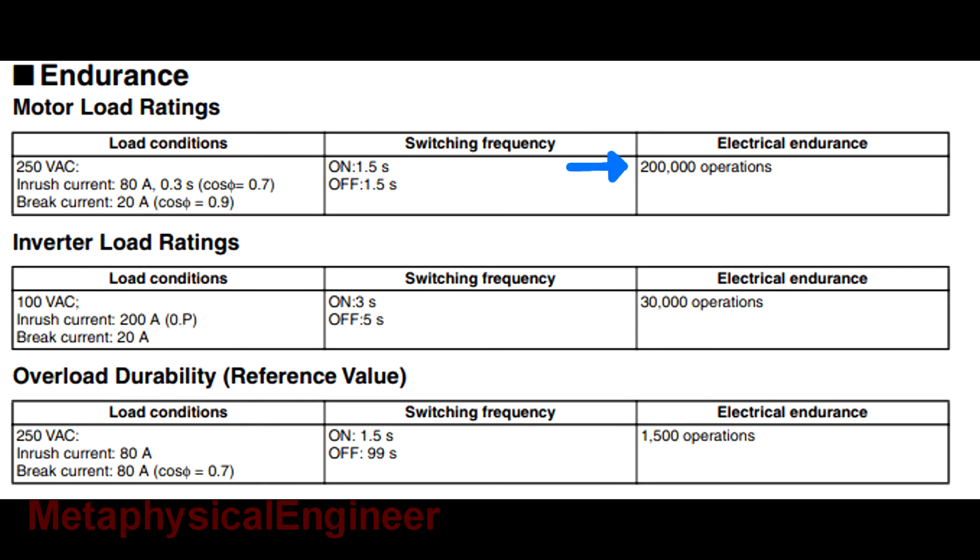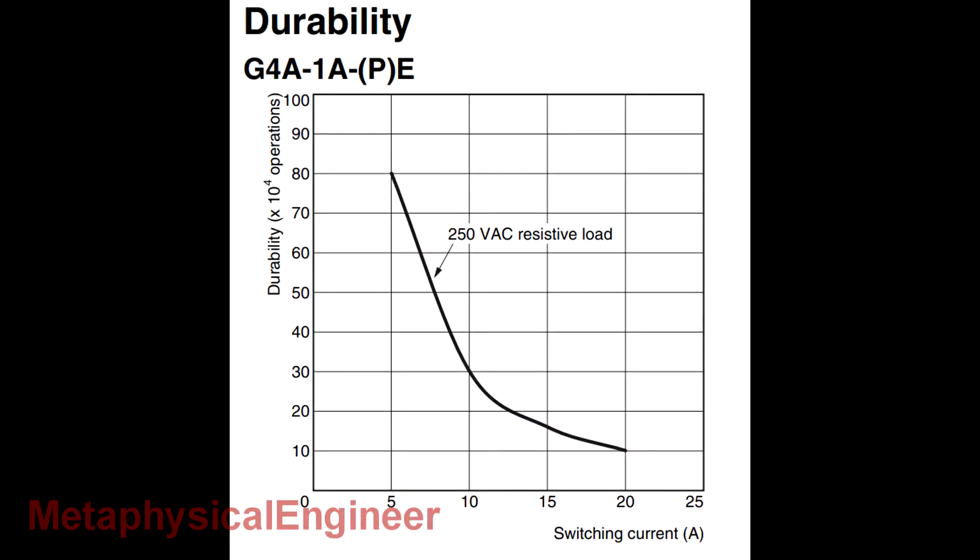this one's rated for 200,000 cycles. Even switching an inverter which really hammers it with inrush, it manages 30,000 cycles. Interesting enough, the resistive load chart is a bit more conservative, but I might trust this one a little bit more given the other listed conditions.